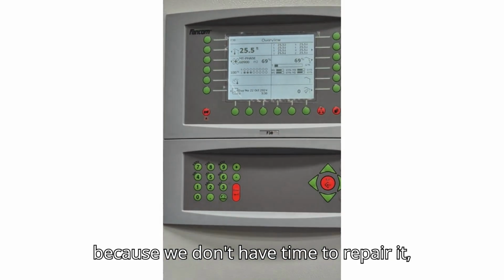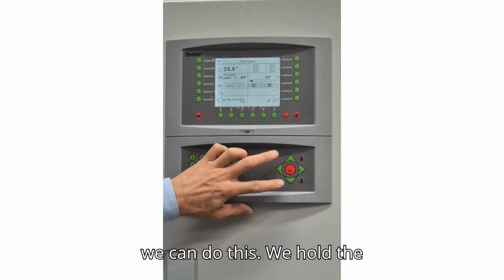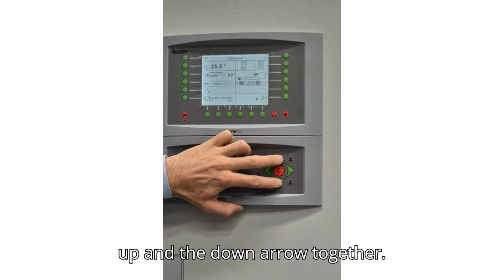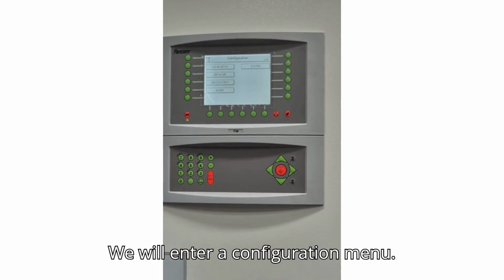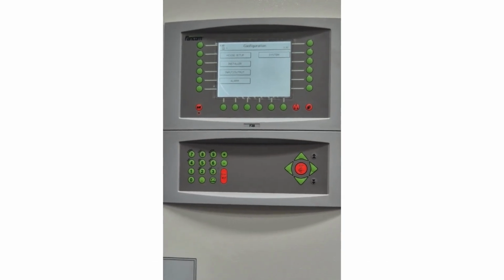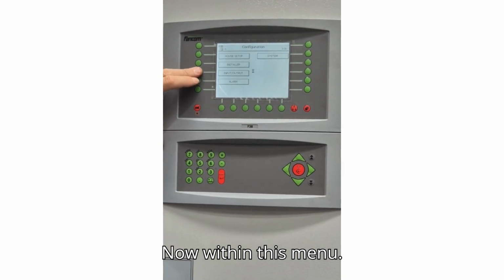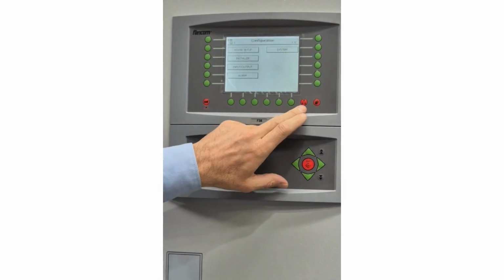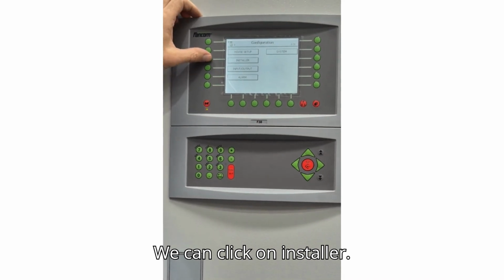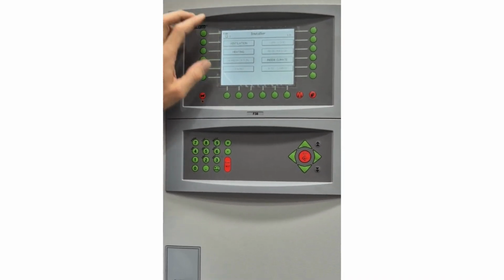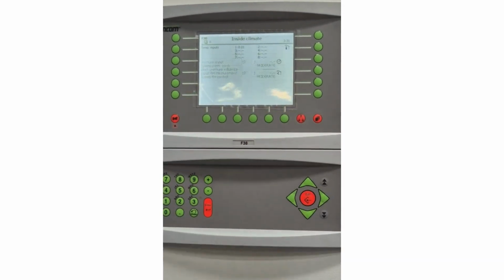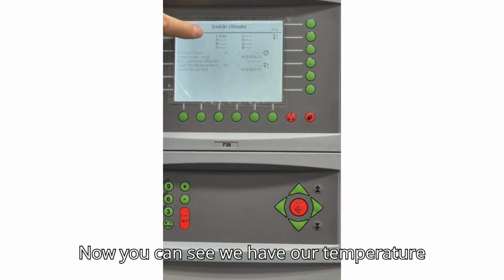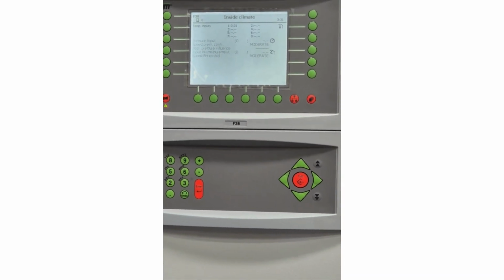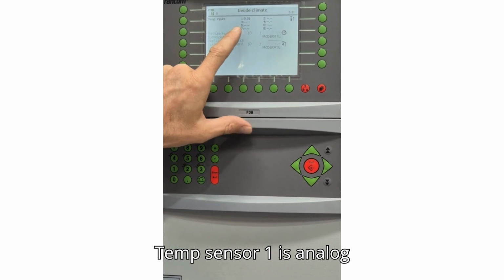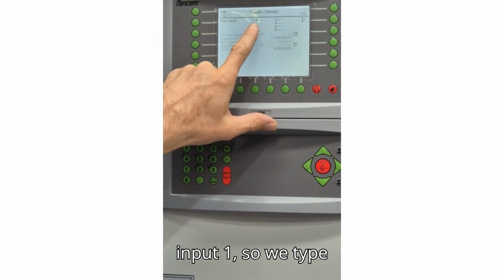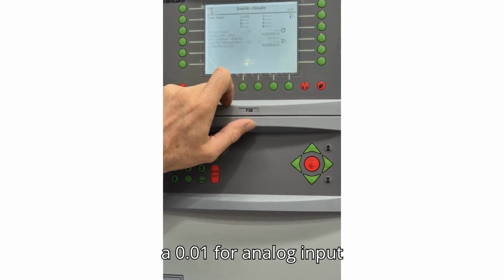So we can check our sensors from here, but if we want to remove that sensor from the program because we don't have time to repair it, we can do this. We hold the up and the down arrow together. We will enter a configuration menu. Now, within this menu, we can click on Installer. We go across to Inside Climate. Now you can see we have our temperature inputs here. Temp sensor 1 is analog input 1, so we type a 0.01 for analog input 1.